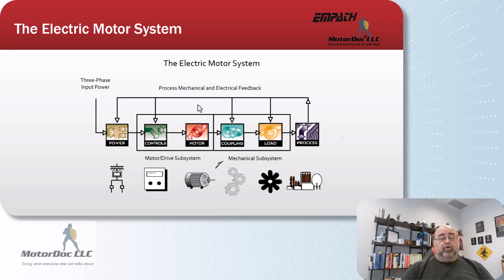What's particularly important, and I emphasize this because there were a lot of vibration folks at the EPRI conference, was that electrical signature and current signature analysis are literally vibration analysis. We just utilize the air gap of the machine as our transducer. This results in the fact that we do not get a lot of the resonances and other conditions that occur in the machine through the material of the machine, so that when we're looking for absolute numbers, not multiples of that number.